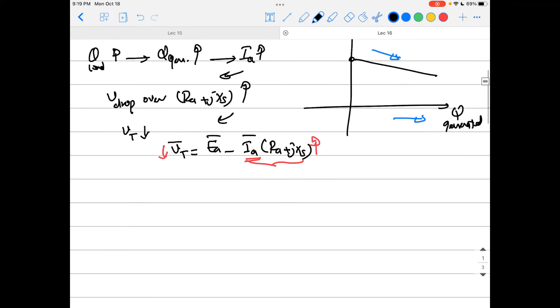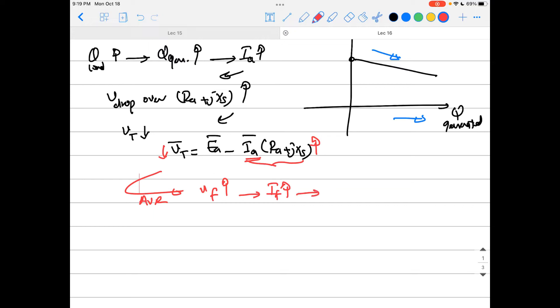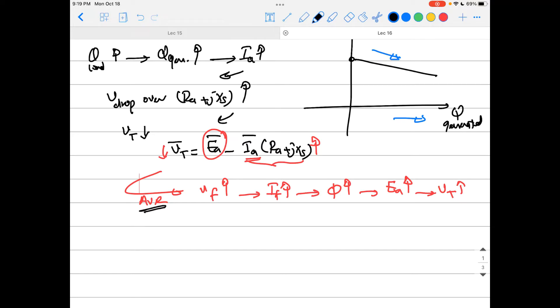To mitigate this, we use the AVR — the Automatic Voltage Regulator — which increases the voltage of the field winding, which increases the field current, which increases the magnetic field, which increases the internal induced EMF. This brings the terminal voltage back up. That is the action of the AVR: it controls the flux excitation of the machine.